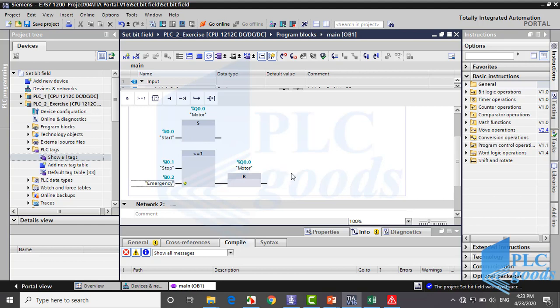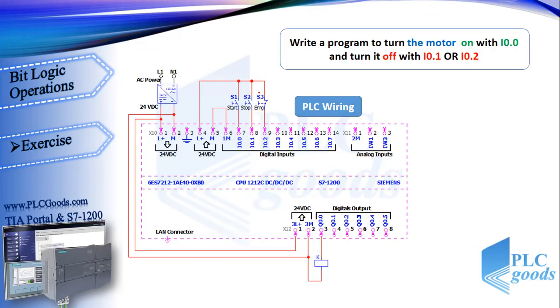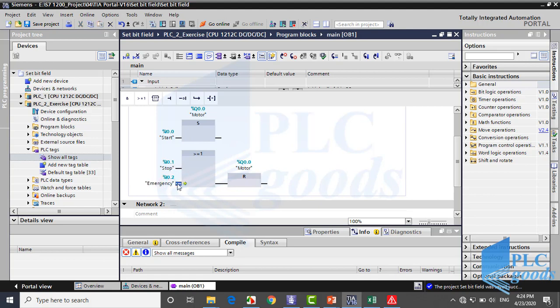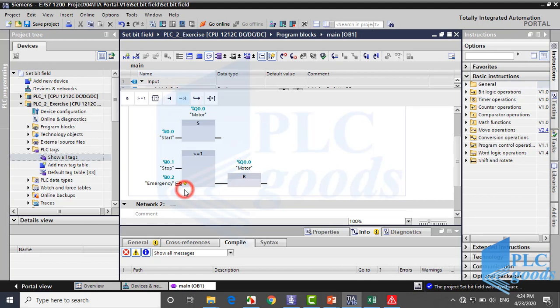This program won't work correctly, why? See PLC wiring again. We've used a normally closed push button for emergency instead of normally open, so in usual conditions the I0.2 address will be 1. Thus this program turns the motor off in usual conditions, and also if it is pressed in emergency conditions, this program won't reset output. Here we must invert I0.2 address. In ladder language we've used normally closed contacts, here in FBD language we can use this icon, invert RLO, for inverting result of logic.